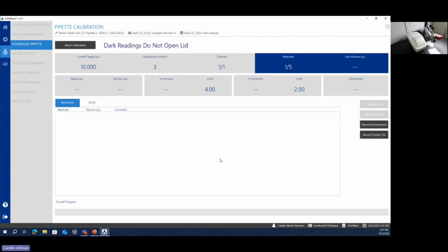And then I'm just going to wait for more instructions from the software. So right now, the system is getting itself prepared. All right, so next I'm being asked to scan a blank vial. So that blank vial, this is the vial that I dispense all of my red dye into. So I'm going to go ahead and scan that. A couple of pieces of information about this blank vial. If I was testing 10 microliters, I could get 40 data points into that one blank vial. I just keep adding the red dye, until the system tells me to change the vial. If I'm testing 1,000 microliters, I can get 5 data points in that one blank vial.